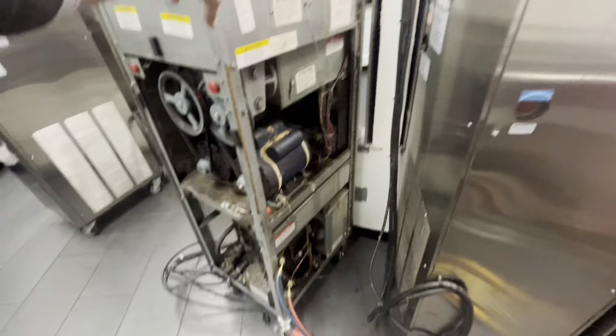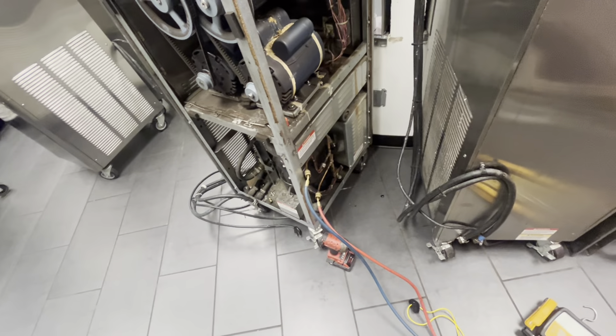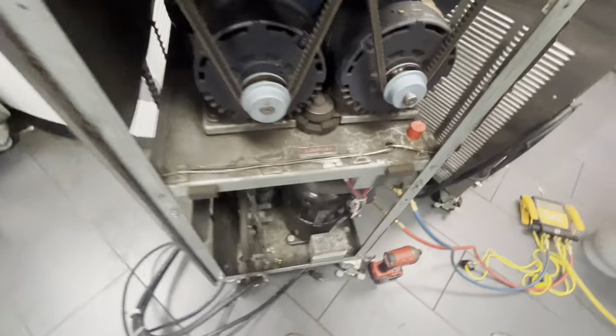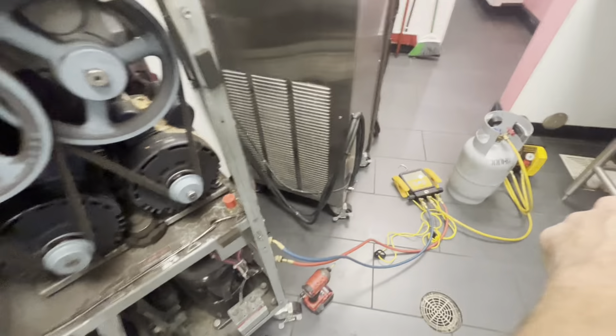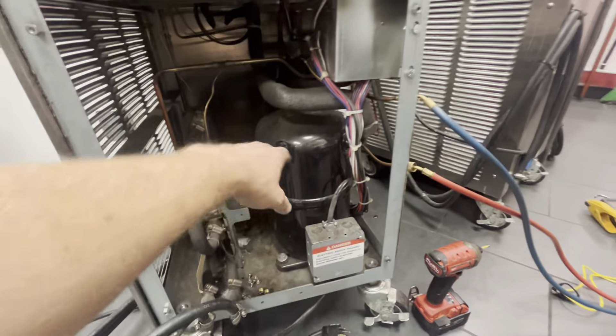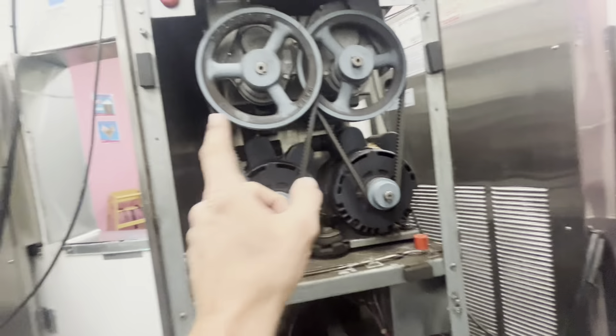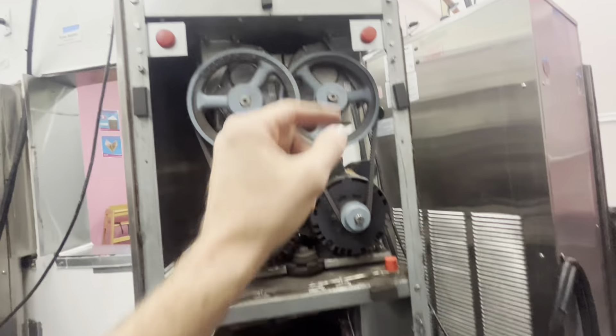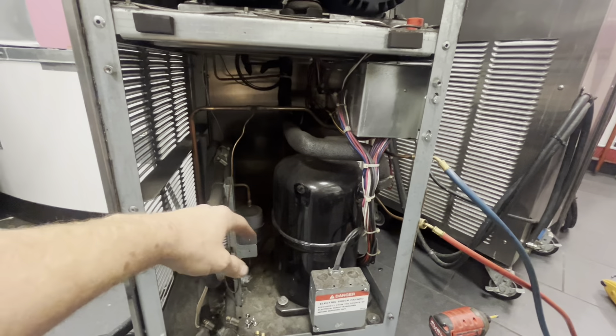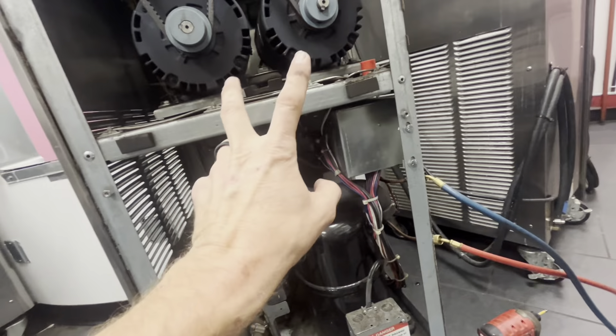We've got a Stoelting soft-serve machine with a very tired compressor, so we're pulling the charge now. The pressure's fine — it's only three pounds, so I knew that wouldn't be a problem. On these units, one compressor runs both of the barrels and the hopper, and we're having a really rough time with this unit specifically when both barrels are running.